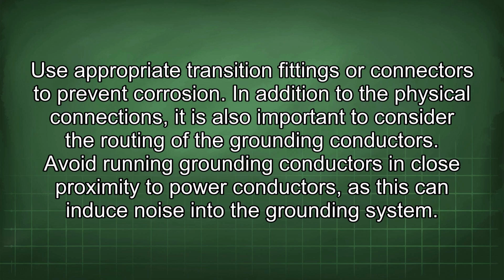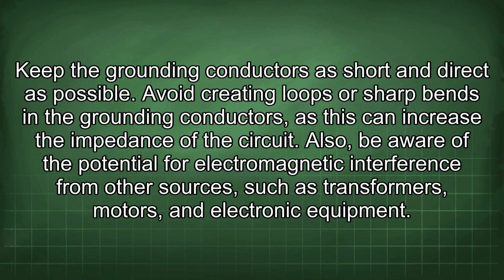In addition to the physical connections, it is also important to consider the routing of the grounding conductors. Avoid running grounding conductors in close proximity to power conductors, as this can induce noise into the grounding system. Keep the grounding conductors as short and direct as possible. Avoid creating loops or sharp bends in the grounding conductors, as this can increase the impedance of the circuit.